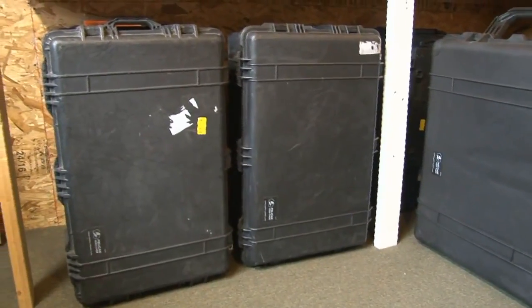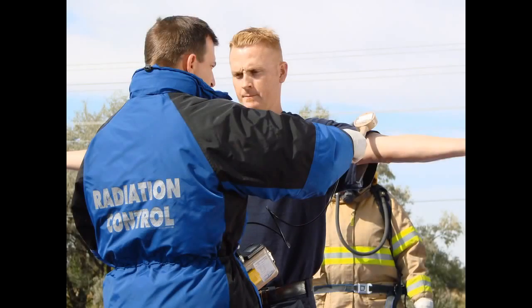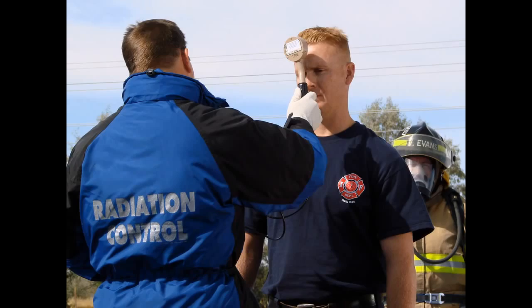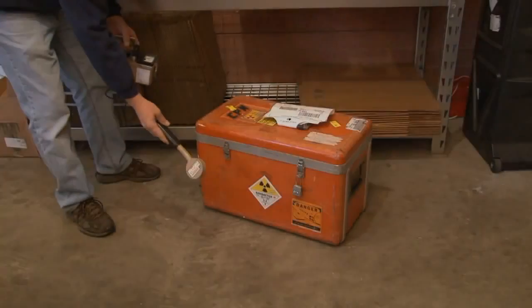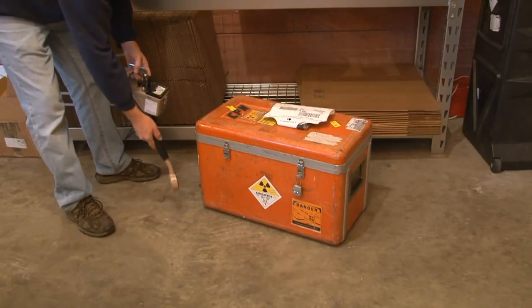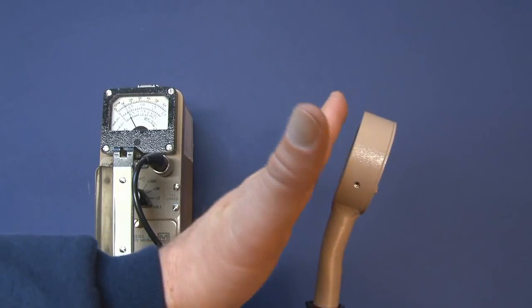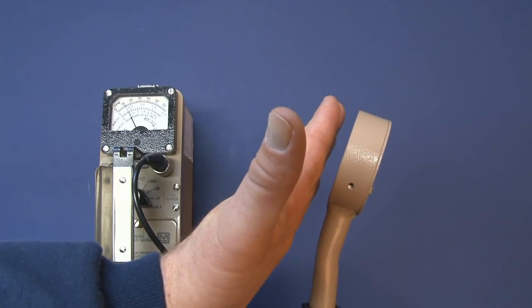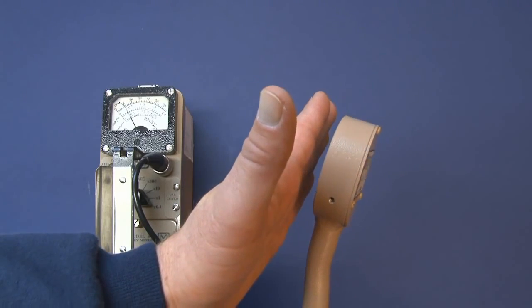This detector is a really good choice for surveying personnel and equipment for radioactive contamination. But I think, as any health physicist will tell you, it's not such a great choice for taking radiation measurements. To use this detector for what it's ideally suited for, which is contamination monitoring, the probe should be held about a ½ inch away from the surface you're surveying and moved about 1 to 2 inches per second.